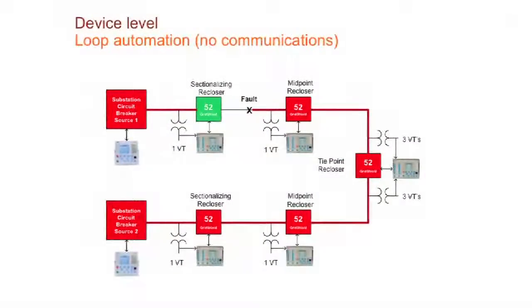this one will close, and you'll basically detect the fault again. And because you've changed the settings and you have the right coordination, this one will detect the fault. It automatically trips, so it won't go to lockout. It won't do the reclosing sequence because it turned on. After the timer expires, it changed settings to have the proper coordination, and then it blocked the reclosing. So it detected the fault and it went to lockout automatically. So that's voltage-based schemes, or loop automation.